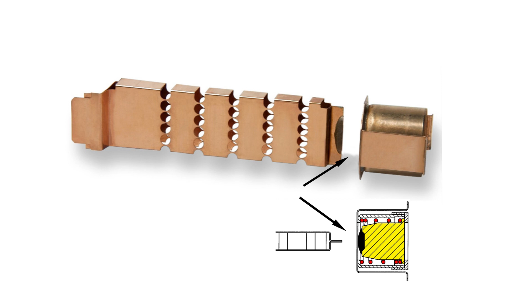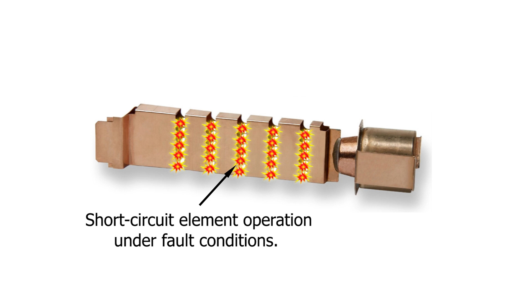For fault conditions, the short-circuit element is designed with minimum metal in the restricted portions to greatly enhance the fuse's current limitation and minimize the let-through current. Fault current causes the short-circuit element's restricted portions to quickly vaporize and commence arcing. The arcs burn back the element, resulting in longer arcs that reduce the current. This is aided by the arc-quenching filler, forcing the current to zero.